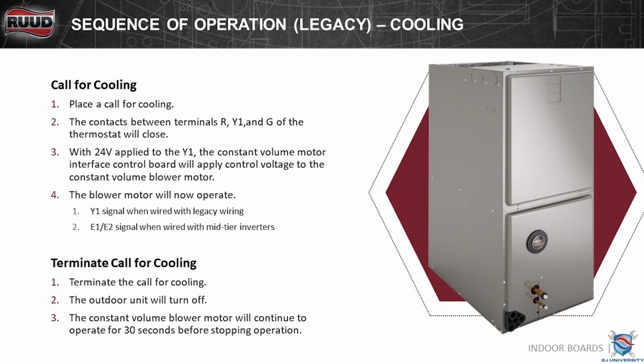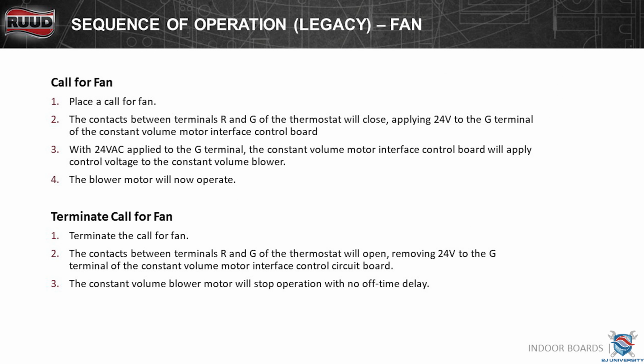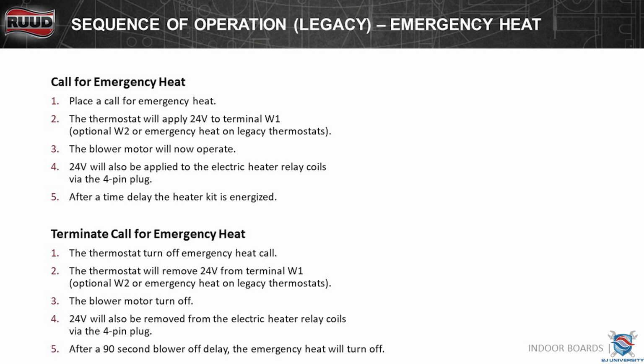So just a little bit about the sequence of operation. The one thing to know is if you're in legacy, you're going to get a Y1 call. But if you're using that 15, 16 AC or 16 heat pump, it's going to energize E1 and E2. That makes sense? Call for fan. Pretty basic. Call for fan is a call for fan. Emergency heat, you're going to get the W1 call, and it'll bring on your electric heat.